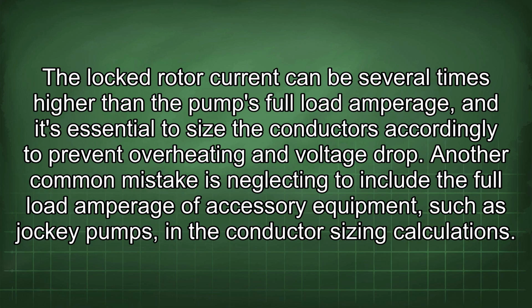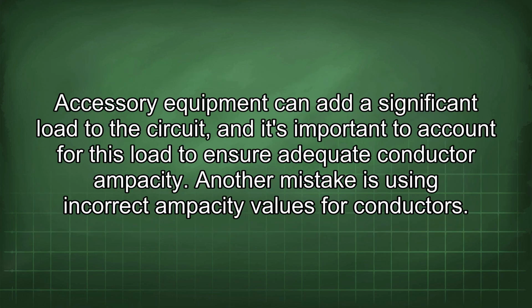Another common mistake is neglecting to include the full load amperage of accessory equipment, such as jockey pumps, in the conductor sizing calculations. Accessory equipment can add a significant load to the circuit, and it's important to account for this load to ensure adequate conductor ampacity.